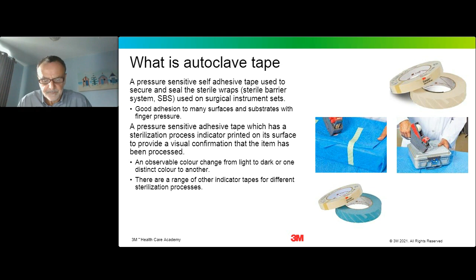I should add at this point that there are other tapes for other sterilization processes available. So autoclave tape for steam sterilization is not unique. You can get indicator tapes for ethylene oxide or for hydrogen peroxide or for other sterilization processes that you might be using.